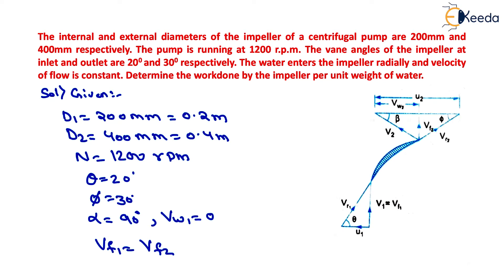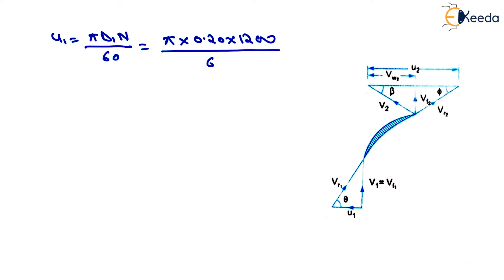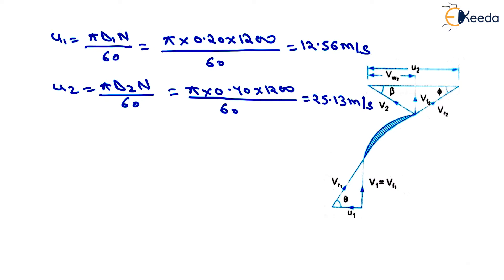Tangential velocity of the impeller at inlet: u1 equals pi times D1 times N divided by 60. Putting in the values — pi times 0.20 times 1200 divided by 60 — gives u1 equals 12.56 meters per second. Similarly, u2 equals pi times D2 times N divided by 60, which is pi times 0.40 times 1200 divided by 60, giving u2 equals 25.13 meters per second.